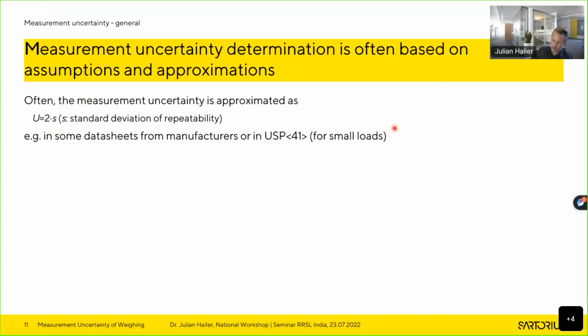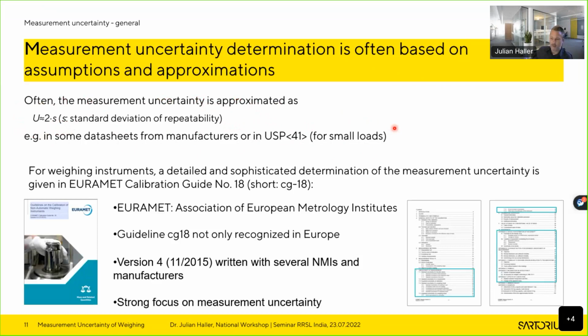If you want to have a better approximation, I personally recommend this Euramet calibration guide number 18. That gives a really detailed and sophisticated description of how to determine the measurement uncertainty of a weighing instrument. The publisher Euramet is the Association of European Metrology Institutes, but we do know, as also a globally operating company, the guideline CG18 is not only recognized in Europe, it is also used in Asia, the Americas, so it is quite a global, don't let me call it standard, but global guideline. And the current version that was published end of 2015, it's the version 4, was actually written with several NMIs.